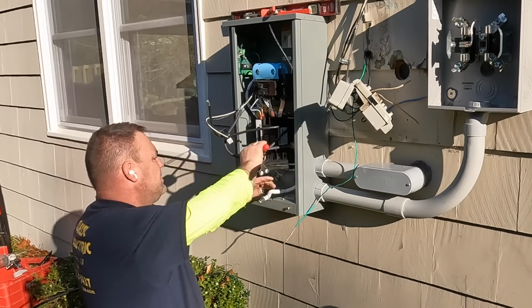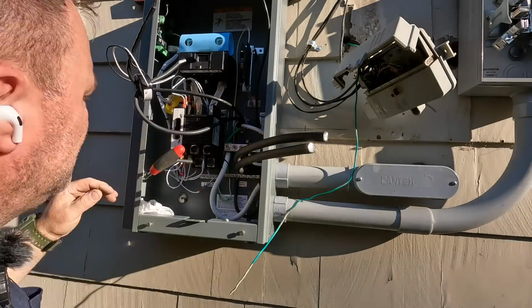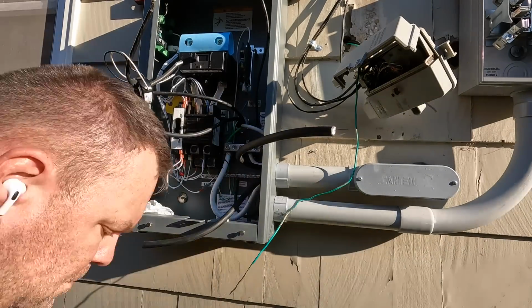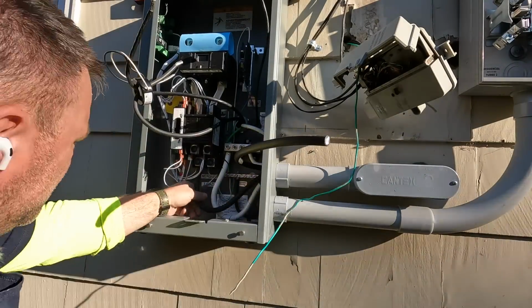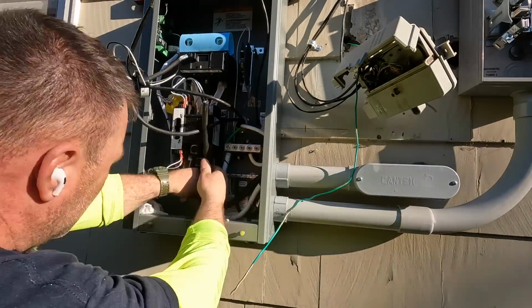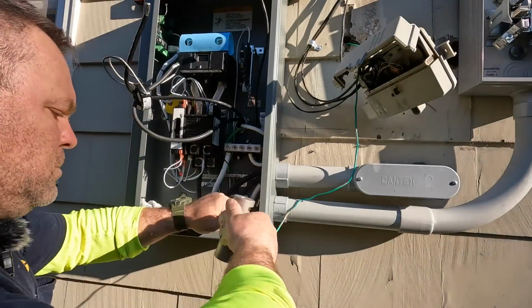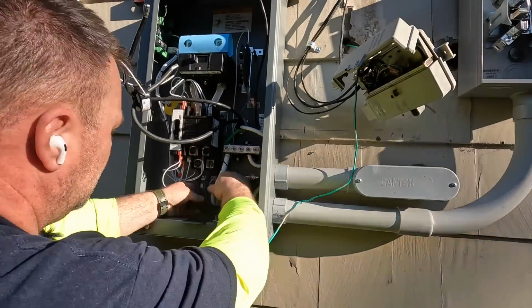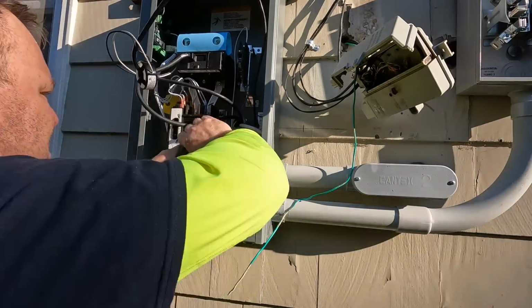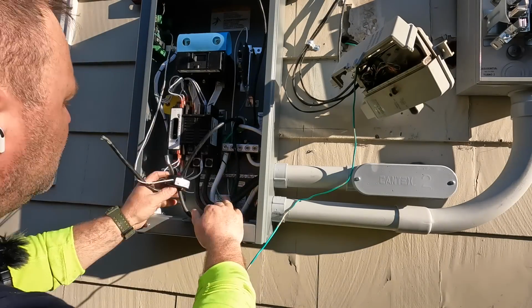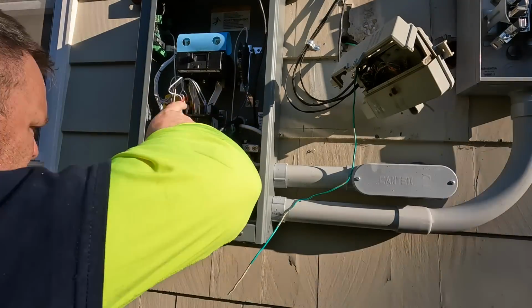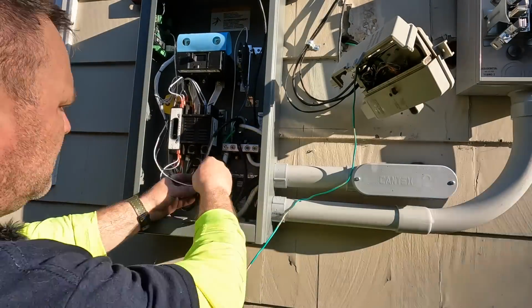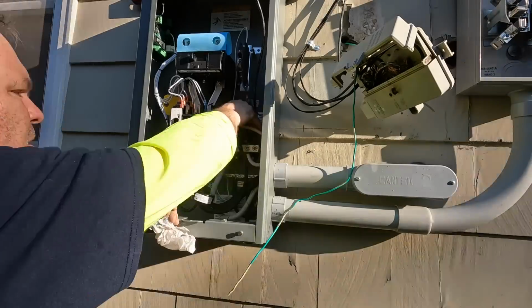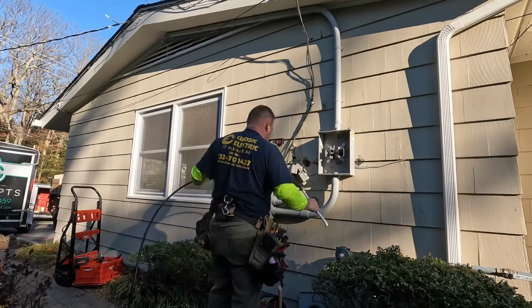The most important thing to remember when sizing conduits and using conductor sizes is every electrical conductor makes heat. So anytime you have wiring going through conduits or anywhere, you have to consider the heat factor. And so what the National Electric Code says, anything more than 3 current carrying conductors in a conduit, we have to start derating them, which means there's a column in the ampacity table in 310.16. Usually we use the 90-degree column depending on the conductor and the insulation type to find out what we need to start deducting from that particular conductor, and of course how many conductors we have in the conduit.